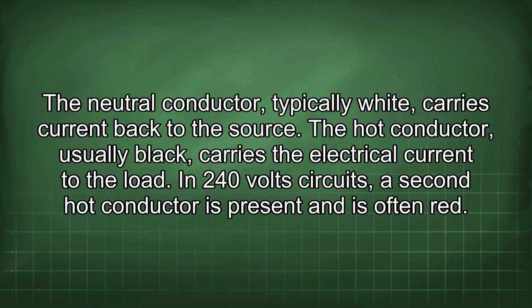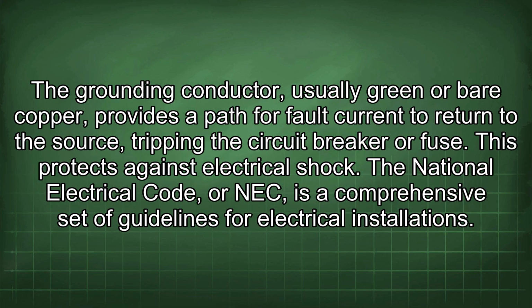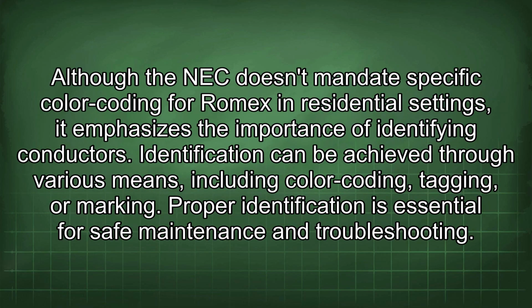In 240-volt circuits, a second hot conductor is present and is often red. The grounding conductor, usually green or bare copper, provides a path for fault current to return to the source, tripping the circuit breaker or fuse. This protects against electrical shock. The National Electrical Code, or NEC, is a comprehensive set of guidelines for electrical installations. Although the NEC doesn't mandate specific color coding for Romex in residential settings, it emphasizes the importance of identifying conductors. Identification can be achieved through various means, including color coding, tagging, or marking. Proper identification is essential for safe maintenance and troubleshooting.